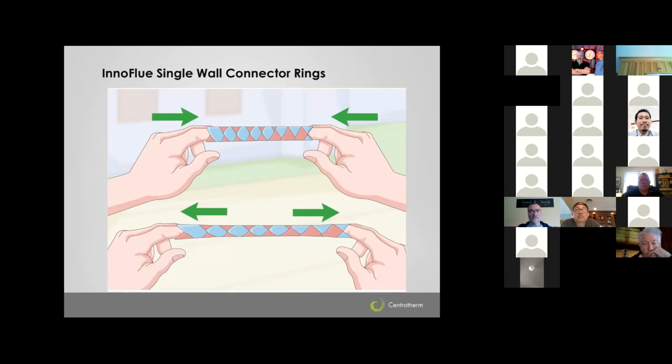The question is, how far on the male pipe end do you spread Centrotherm? No, just the very, very tip, Frank. Less than a half an inch, a quarter of an inch, half an inch at the most. It's just putting a dollop on your fingertip and wrapping it around that fitting, just to enter and slide past that gasket. That's where the resistance is going to be.